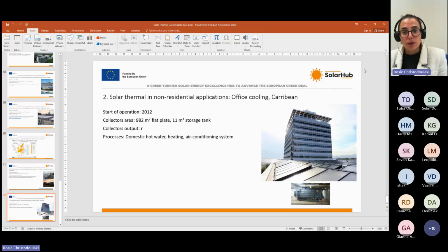Solar thermal systems are also used for office cooling and not heating. In the Caribbean, we see this example. This solar thermal system is used solely for office cooling purposes, and to a lesser extent for domestic hot water and heating. This system started its operation in 2012. It consists of approximately 1,000 square meters of flat plate collectors and also has a storage tank capacity of 11 cubic meters. And as I said before, the bulk of the heat production is used for office cooling.